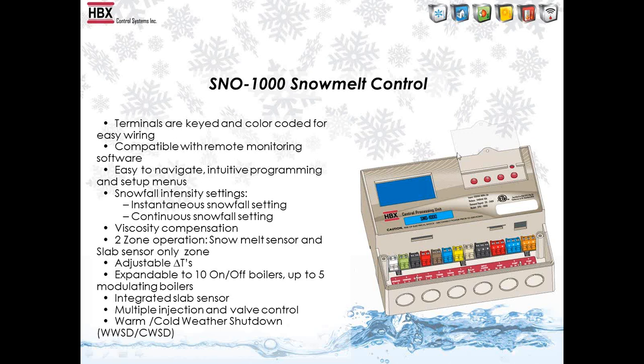One of the big differences between this and the smaller system is the color coded and keyed terminal blocks. Obviously very easy to wire, so everything's line, neutral, ground in. Your pump outputs actually have 120 volts coming out of them. It's intuitive and easy to program, everything's in plain English. Four buttons, it programs just like our CPU 1000 and our Eco 1000. So if you know those products, you'll know this product very easily.